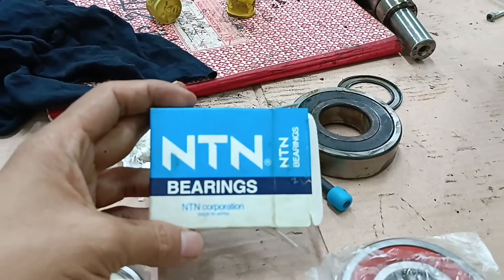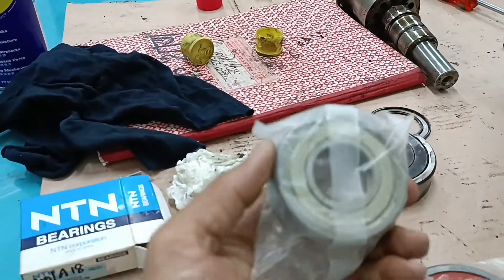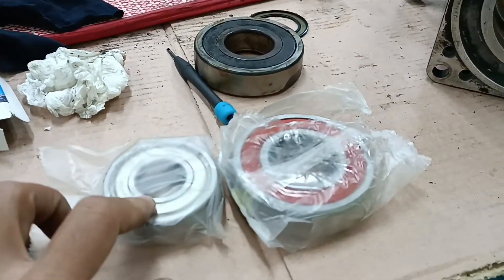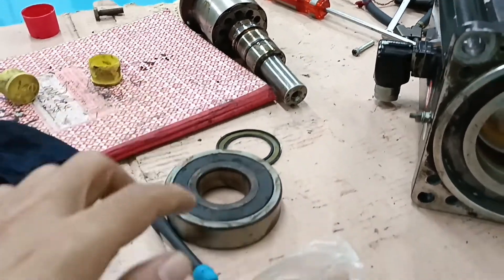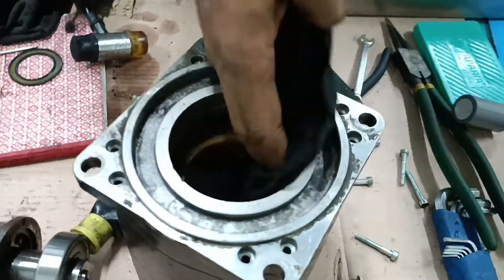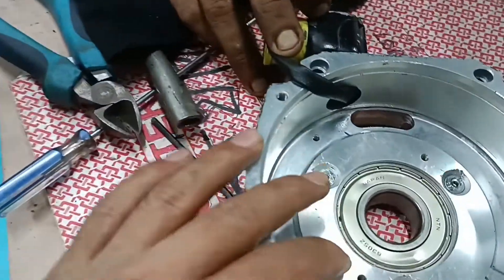I am using NTN brand replacement bearings. The non-drive inside bearing is 6305 and the drive-side bearing is 6307. I am fixing both bearings in the rotor — sorry, this is the rotor. I am cleaning the full stator of any dust. I have already fixed the non-drive inside 6305 bearing and fully tightened it, then putting the non-drive inside assembly together.